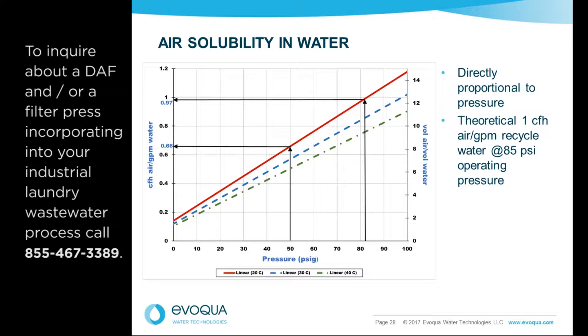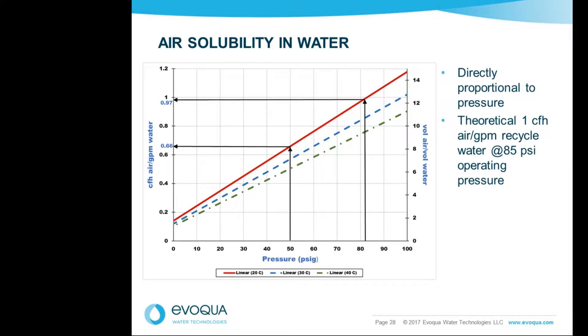The key feature of any DAF is the white water system, which uses pressure and mixing energy to force air into solution with water — typically using a recycle stream from the DAF effluent. Air solubility in water is affected by both pressure and temperature. The amount of air that goes into solution is directly proportional to the pressure exerted, with higher pressure putting more air into solution. This pressure is provided by a recycle pump operating between 50 and 100 psi. Also, higher wastewater temperature lowers the solubility of air in water.